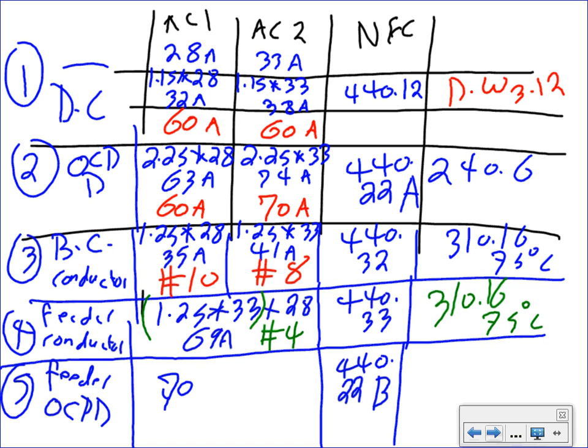70 amp, plus the full load current of all the others, 28. That will get you 98 amps. And if it's not a standard size, you need to go to 240.6 to find the standard. If it's not standard, what do you need to do? It doesn't allow me to go up. You're going to go down. What's 98 down? Do we have 90? 90.